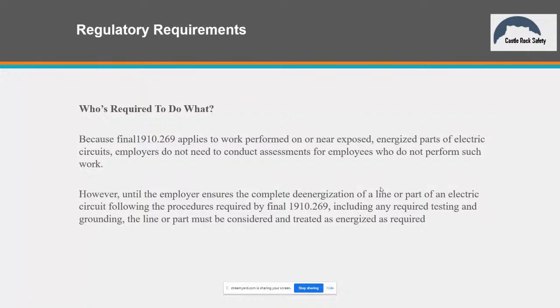What does it mean to be near it? They tell us what that means. Basically, if you're going to work at MAD or closer, then you're exposed. If you're outside of MAD distance, OSHA doesn't consider you exposed, unless you're doing something that could violate the MAD, like switching. So it's just the employees working at MAD distance or closer, or doing something that could cause that arc flash. Again, you don't need to identify by name.